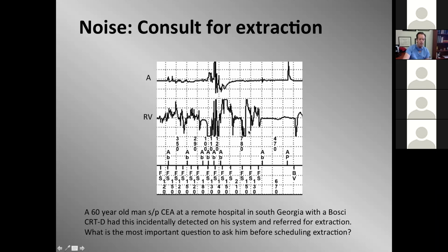Sometimes it's hard if it's a single lead because electrosurgical artifact is very junky, high amplitude, and for all the world resembles conductor fracture noise. And so understanding and remembering to ask about any surgeries or recent surgeries is important. But when you have the advantage of numerous leads, it's usually fairly apparent. It's amazing to me how many people forget that they've had surgeries and how many surgeries occur in the absence of the knowledge of an implantable device.